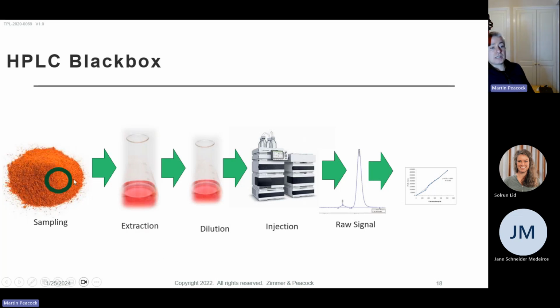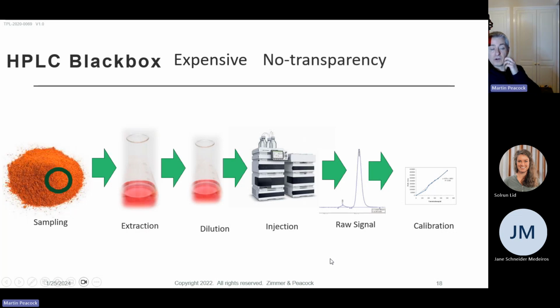But you could say that sampling is a problem, manual extraction is a problem. If you add up all the errors, what I could say about HPLC is it's expensive to own, it's expensive to run, and therefore it's expensive to do tests upon. It's nobody's fault. It's just the way the instrument is. There's no transparency on this, not to the grower. The grower gets a certificate of analysis. They have to believe it. There's no statistical look at the average or the ranges. They just get a certificate with a number on it, and it may have some error associated with it. And I think the error might be plus or minus 25%.